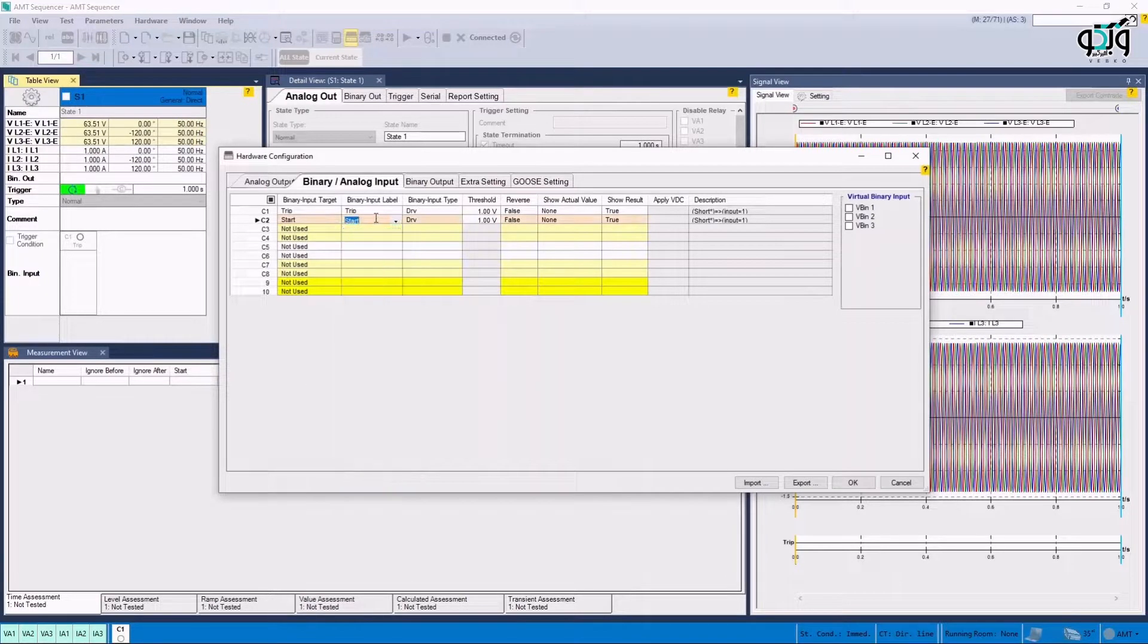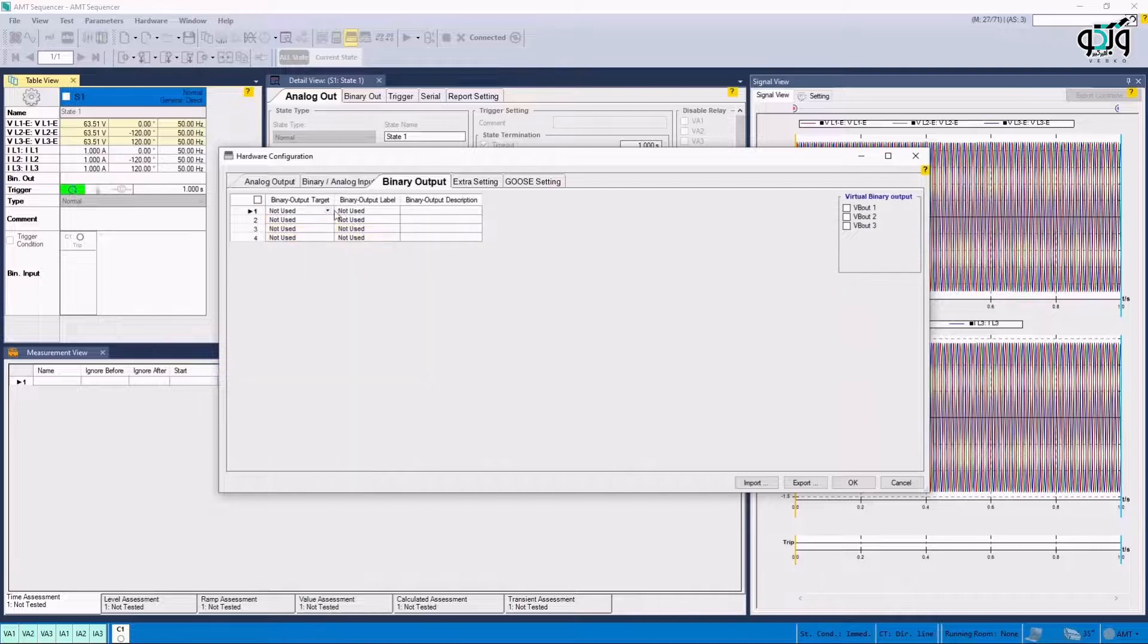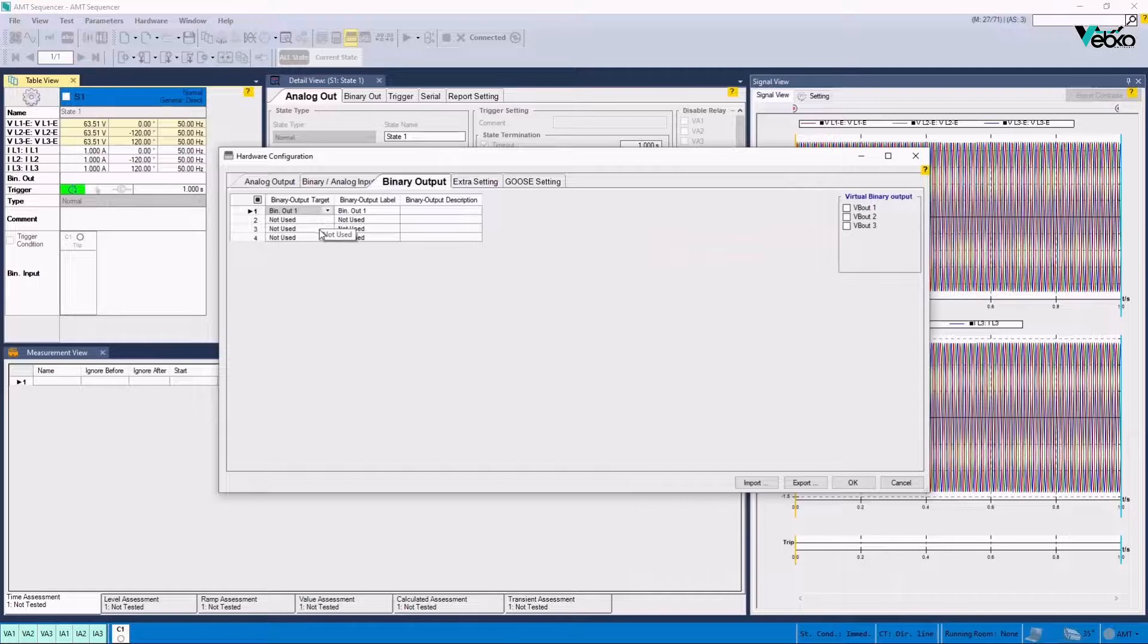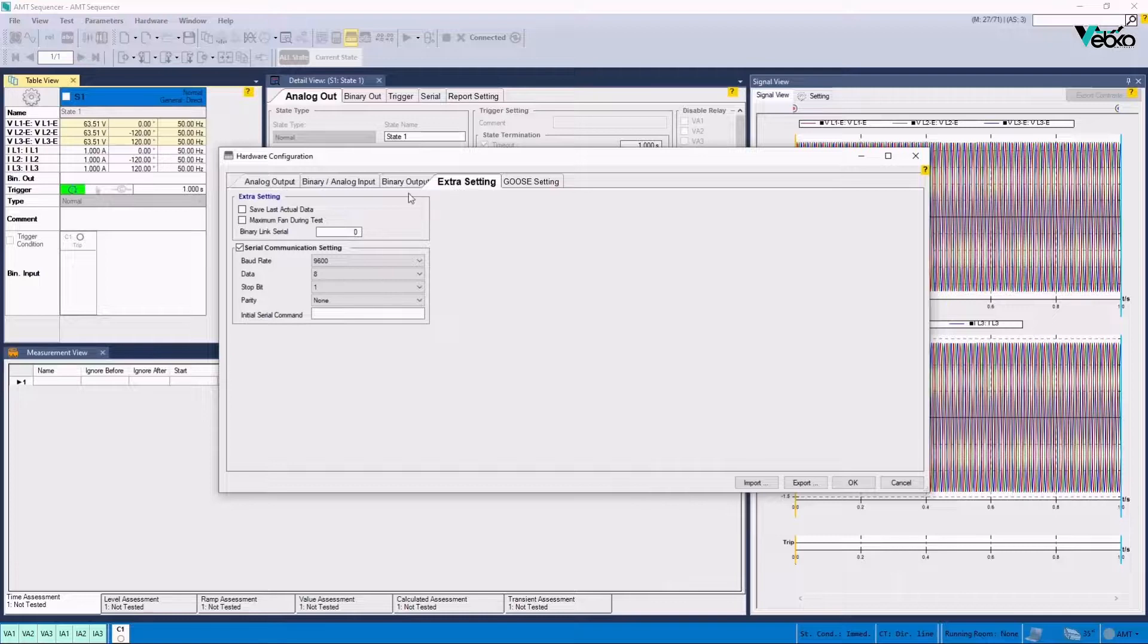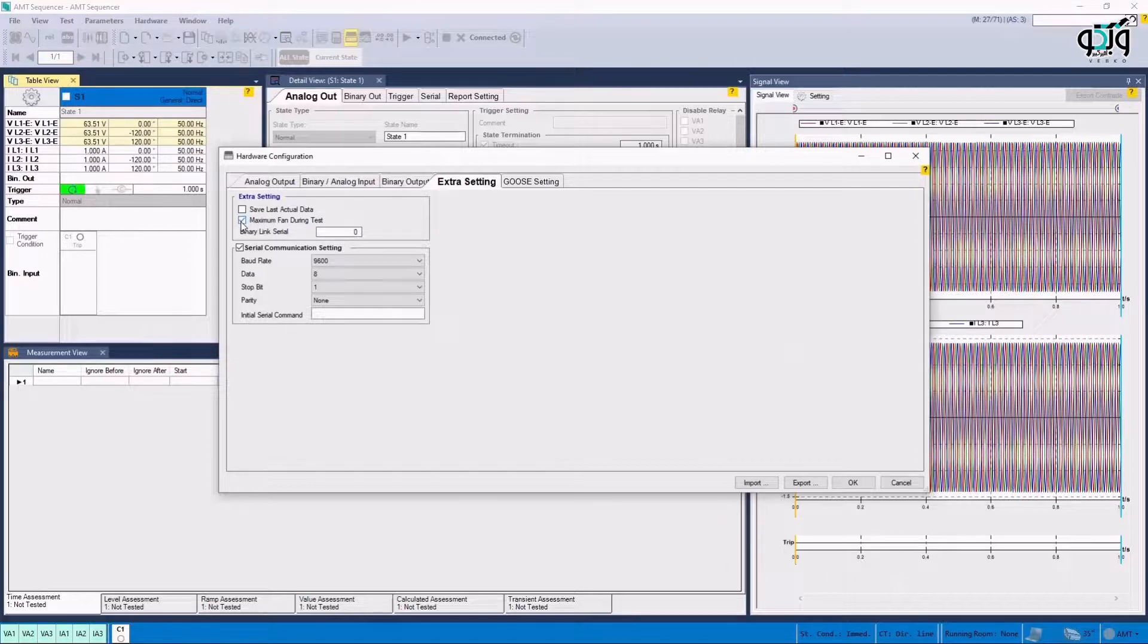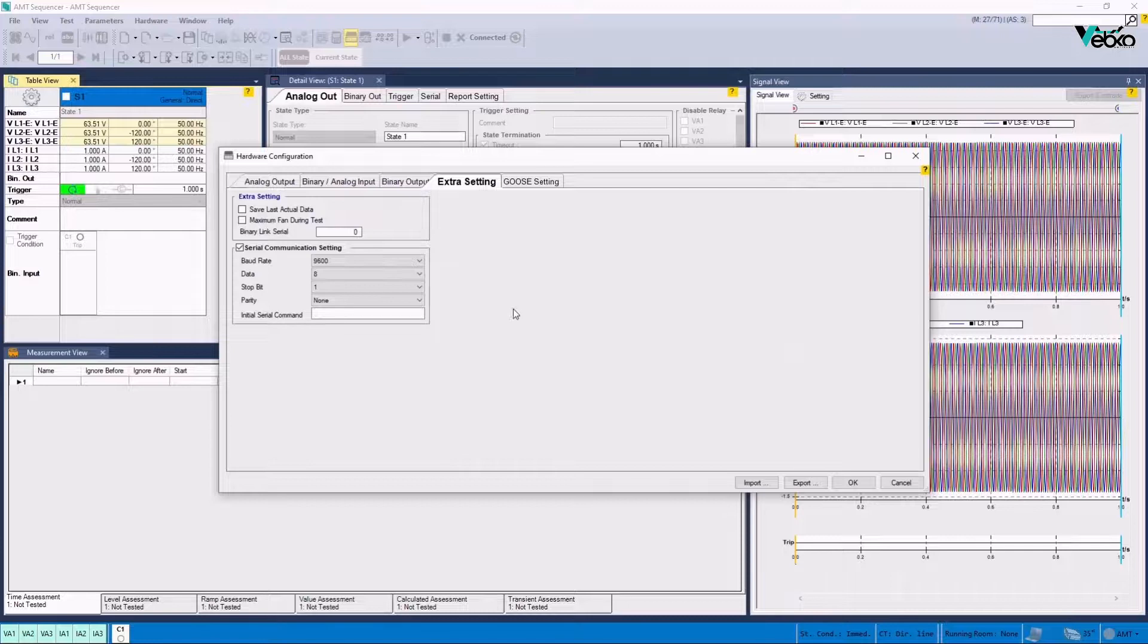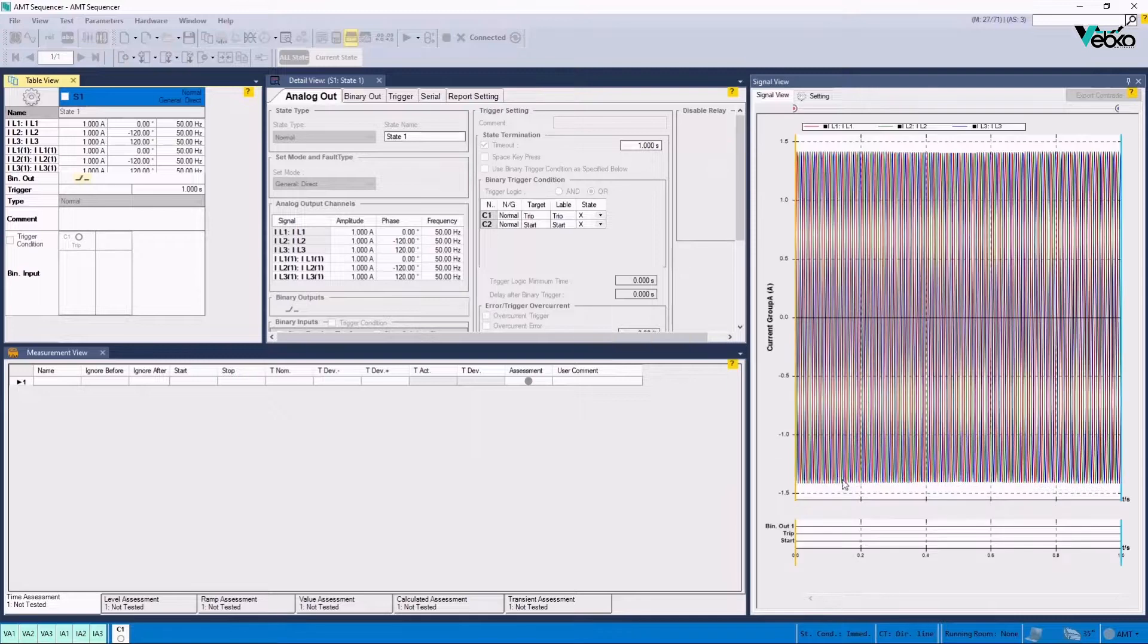If the user wishes to adjust the output signal for reasons such as specifying the state of the key, they can do so by using the binary output header. Save Last Actual Data option in Extra Settings section can be used to save the last injection data. Since longitudinal differential tests, especially in search section, need a long time and this can lead to overheating of the device, it is possible to activate maximum fan during test option, so that the fan works at its maximum speed during current injection and avoids overheating of the device and stopping the test.